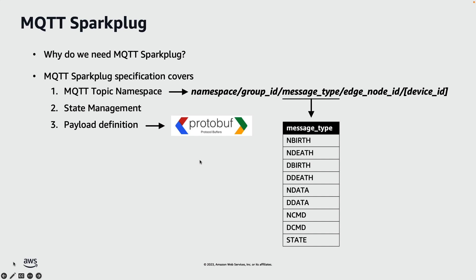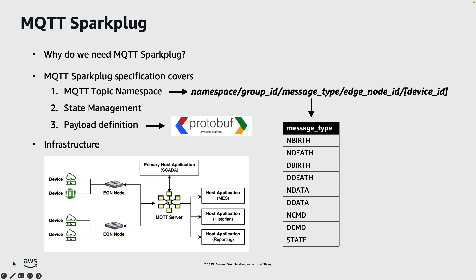Now let's look at the different components that make up an MQTT Sparkplug-based infrastructure. At minimum, only two components are required: the MQTT server, which is basically an MQTT broker, and then a Sparkplug edge-of-network node, which is an MQTT client that offers a local protocol interface to devices like PLCs and RTUs. On the other hand, the primary host is a SCADA system that consumes the data and sends back commands to devices to control the operation. Finally, you can also have other host applications like MES historians to store and visualize the operational data.